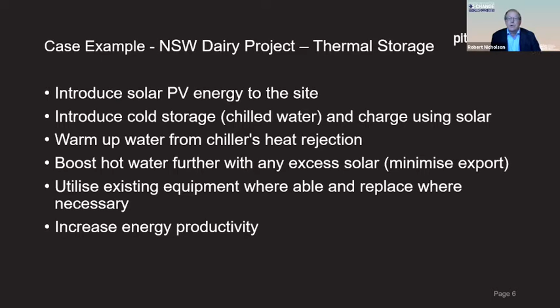Rather than one single site, it's a range of them. At this dairy farm, we're introducing and retrofitting thermal storage into the working dairy, integrating solar PV, which isn't the most obvious fit in a dairy farm. Coupled with that, we've introduced cold storage by way of chilled water, or we could use glycol, which we'll charge using the solar PV. We'll use waste heat from the refrigeration plant to warm up water that will be further boosted to temperature using the solar. Where possible, we'll reuse existing equipment, and replace or add equipment where necessary, which can also result in additional efficiencies. Our goal is to increase energy productivity and better utilize their energy resources.